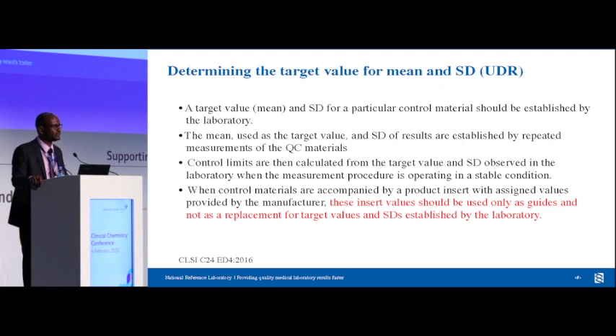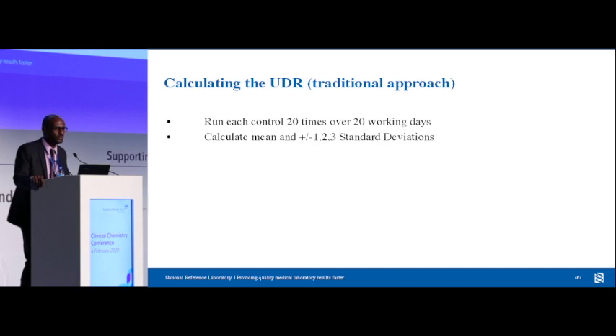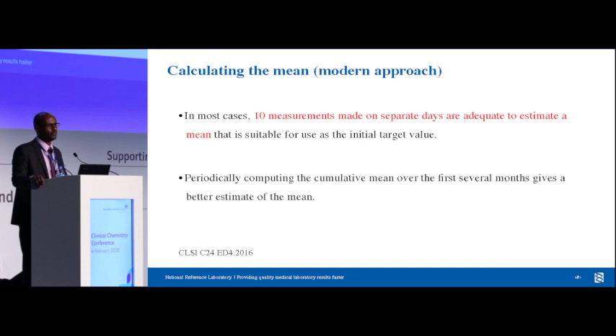The package insert or manufacturer QC values should only be used at the beginning. Once you have enough data, you need to calculate your user-defined ranges. How do we calculate user-defined ranges the way we learned 30 years ago? Run the QC 20 times over 20 days, or two times over 10 days, or four times over five days, and calculate your mean and SD. That's the old way, and most labs are still doing this.